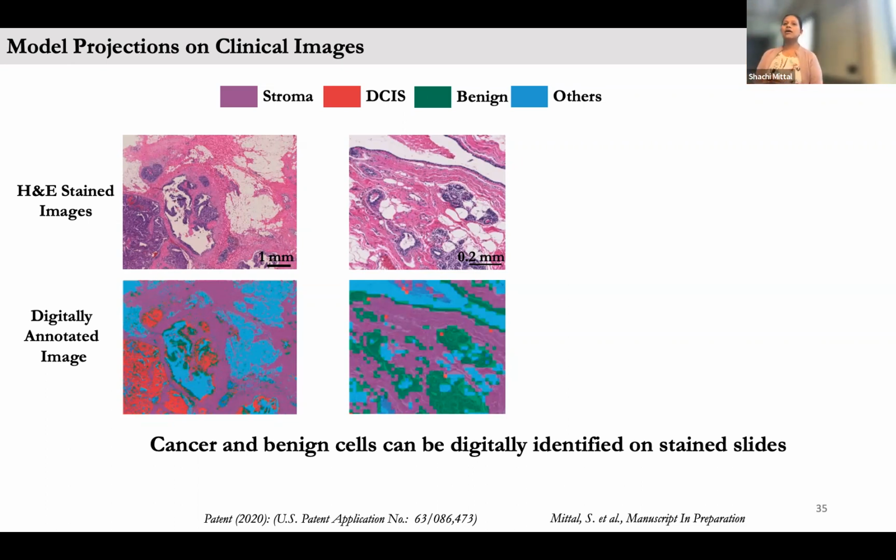Because then there are issues of what can be the percentage inaccuracy, how is that affecting, what are the compliance issues, how does this algorithm input the data? Can you put that on a cloud platform? If you put it on the cloud platform, how can you put patient data on the cloud platform? Will it need metadata or not? Those are the things that you need to do, and then get it approved by an agency to actually become a part of a diagnostic test. So right now, this is a model. It's not a diagnostic test.